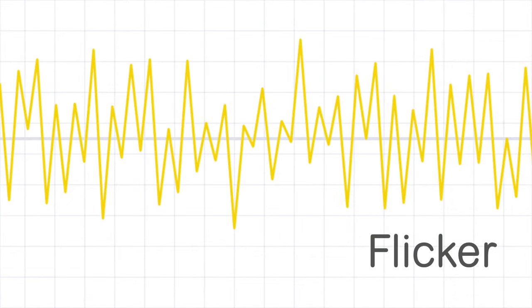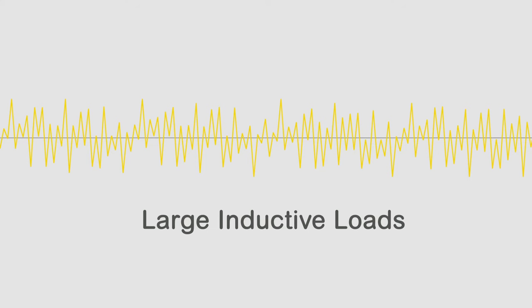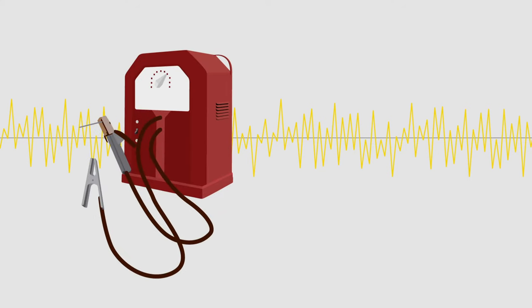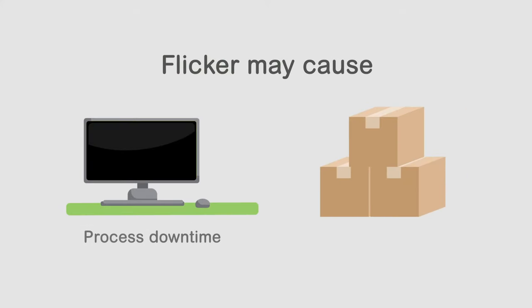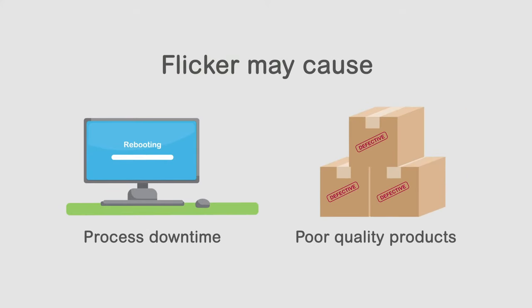Flicker level is discovered by using the short-term flicker coefficient or PST. Flicker is caused by a series of voltage fluctuations and depends on both the magnitude of the fluctuation and the frequency of the fluctuation. Flicker is normally caused by large inductive loads. When a welder strikes an arc or an inductive load starts they demand large amounts of inductive reactive power. That makes the voltage sag repeatedly within milliseconds or seconds. Flicker may cause process downtime or generate poor quality products.